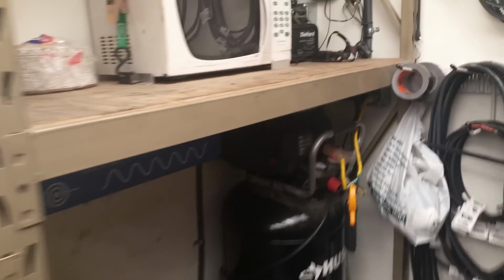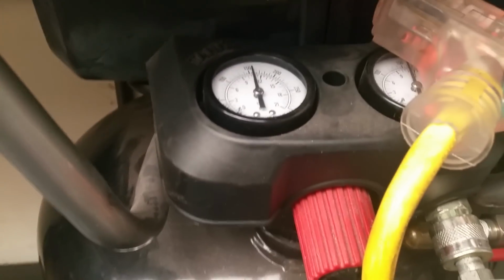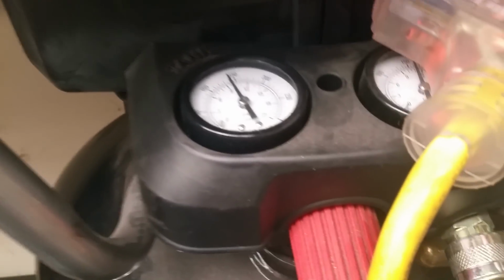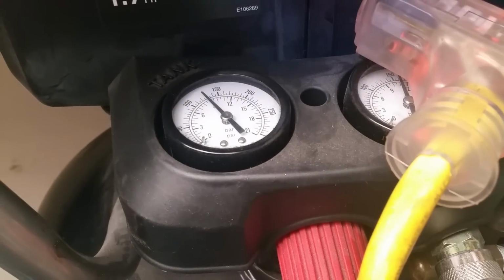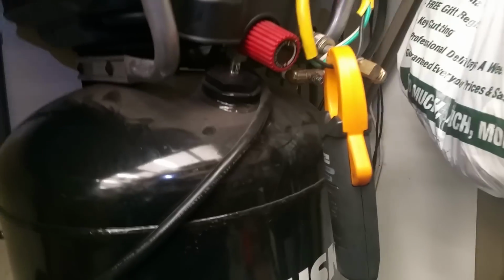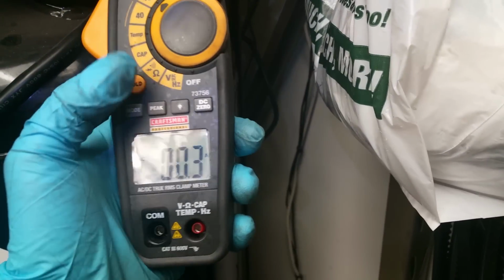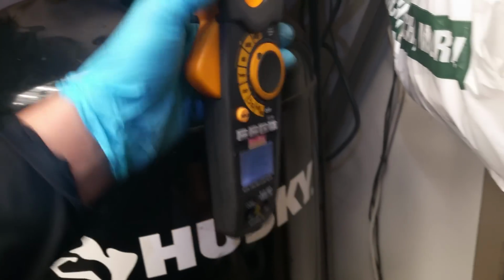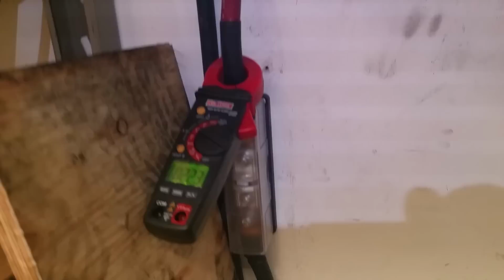Okay, so now I'm going to start up a couple loads so you can see amp draw. We're going to drain a little bit out of the compressor. Very loud, I know. Now we have our amp clamp set on AC amps. We're going to try to catch the peak amp draw when it starts up, because that's your big draw. And right now, with just the lights on, we're drawing 22.3 amps.